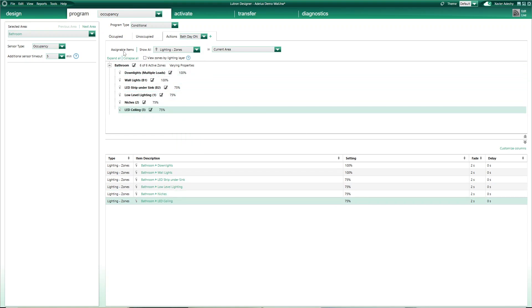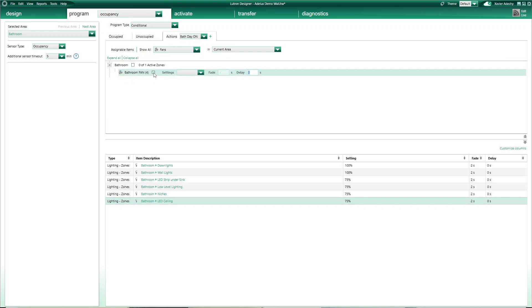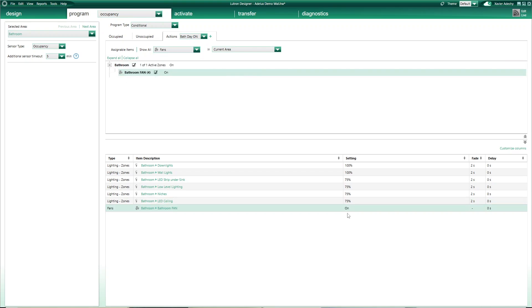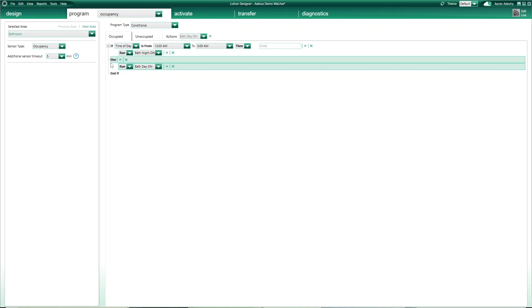Also, in the assignable items here, I select Fans to set my Bathroom Fan On and add it to this action. Back on the Occupied tab, in the Else section, I make sure my new action Bath Day On is selected. So when my bathroom is occupied: if the time of day is between midnight to 5 a.m., I'll run my Bath Night On action. Else — meaning the rest of the time — I'll run my Bath Day On action.